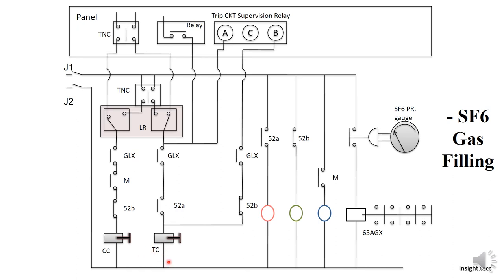Moving on to the tripping circuit: again we have the GLX contact, then auxiliary contacts 52A and 52B, and there is a trip coil. The use of 52A and 52B is — whenever the breaker is in open condition, 52B will remain closed, through which we can get an open indication. Also, the auxiliary contacts 52A and 52B are used for the indication circuit to indicate whether the circuit breaker is on or off.